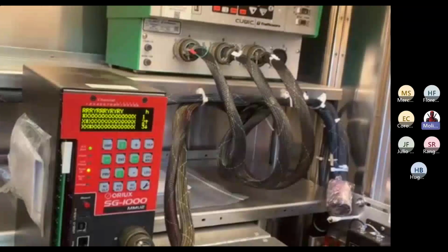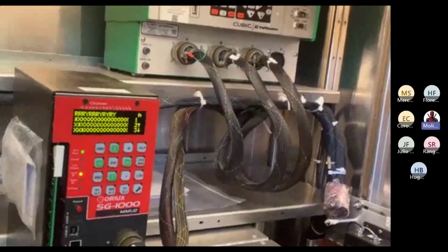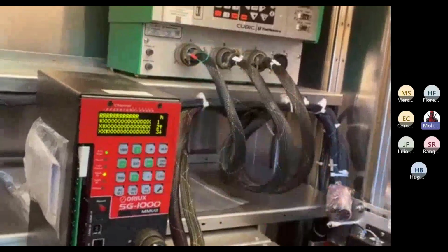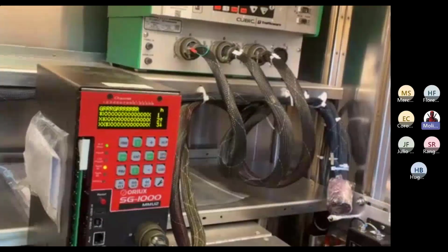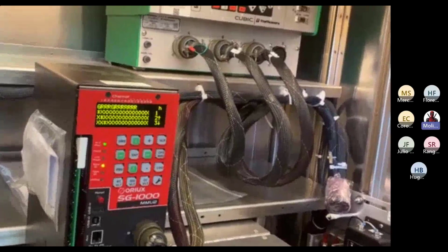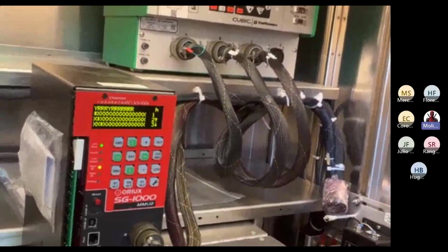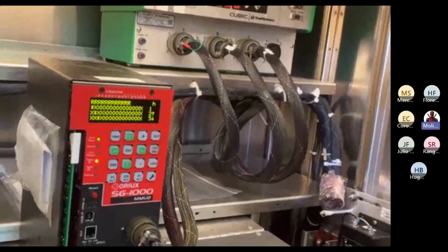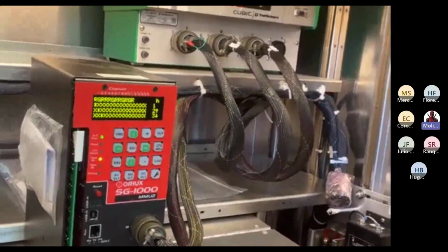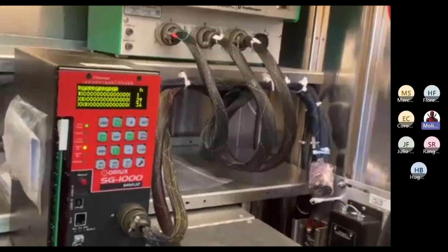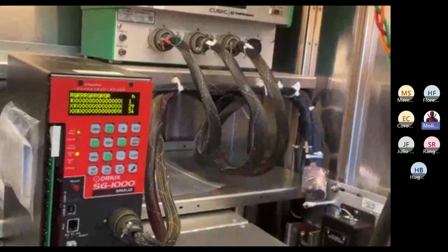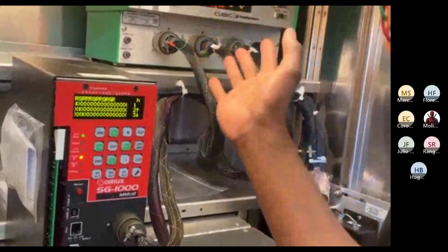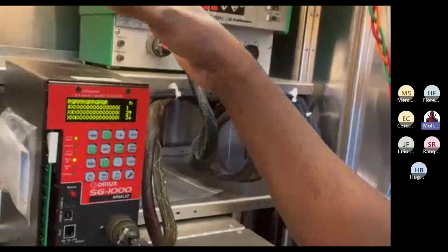Okay, I have to look into that. The information on what should be running together is not coming from the monitor; it's coming from the controller. So unless the monitor is reading it from the controller, I'm not sure how it knows what should run together, other than what you jumper, because that's how the monitor knows what phases can run together. You physically put a jumper in there, letting it know. It all comes from the controller.